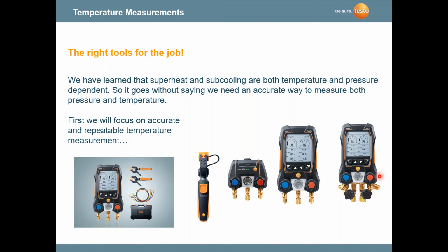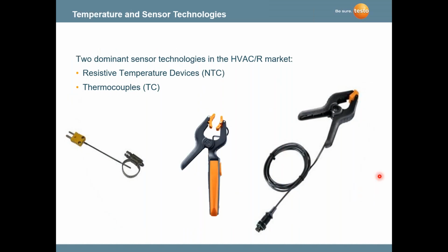So the technology behind what we're using today has certainly changed. We're no longer using as many analog gauges or sling psychrometers. And there's a lot of things to look at. One of the biggest things to look at is the sensor technologies that are available to us today. One of the most important measurements we can do is temperature. And we have two ways of measuring temperature. We have thermocouples, which most of you are familiar with. That would be this one right here, which is based on voltage measurement. And then we have resistance measurement, which is an NTC probe, which are these two probes right here.